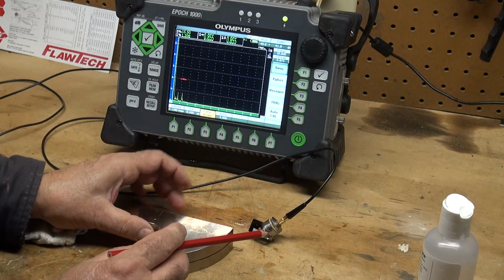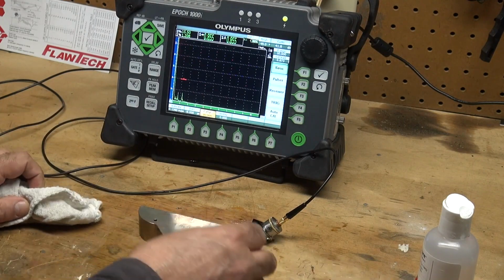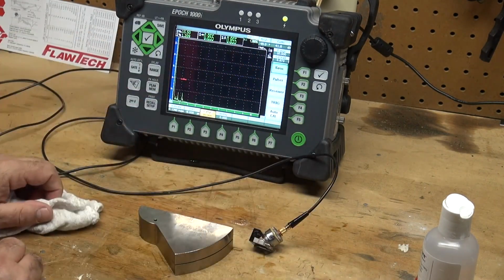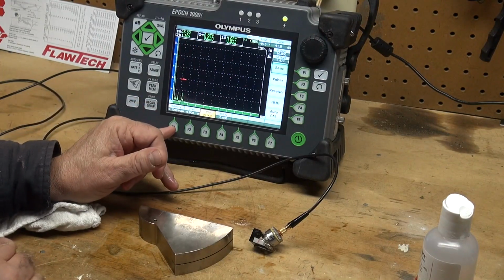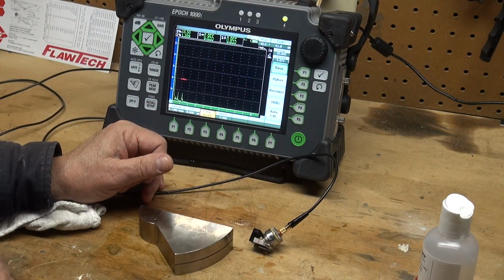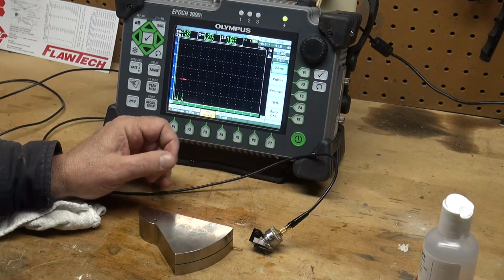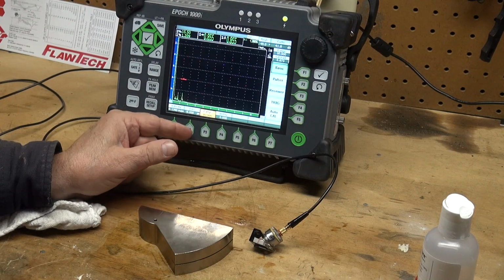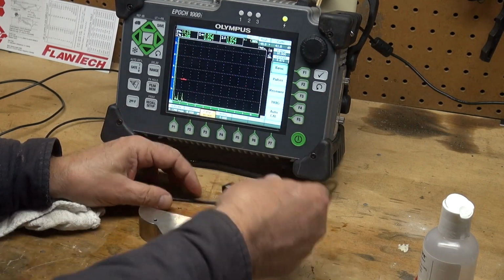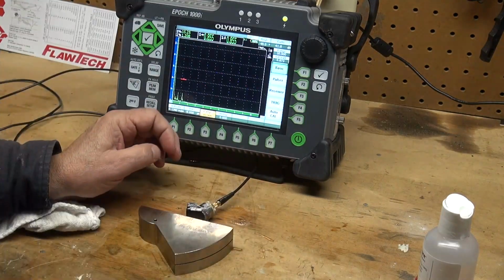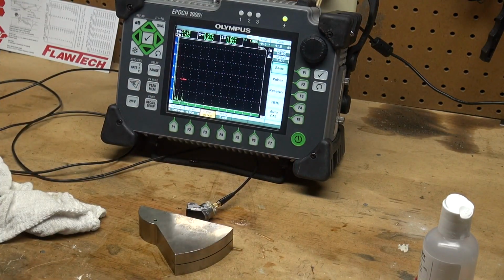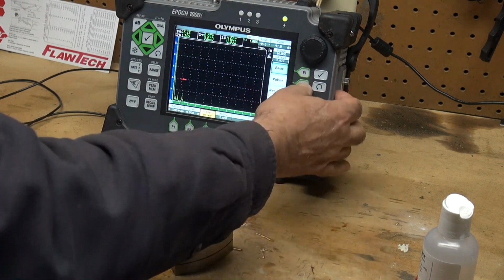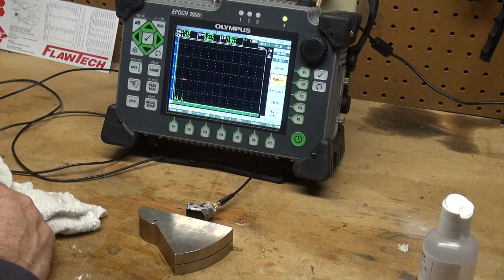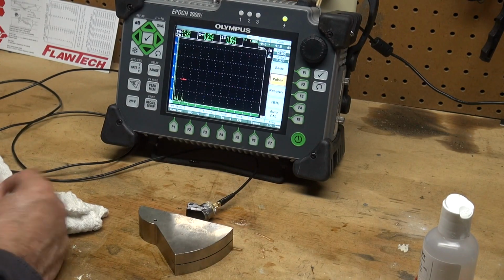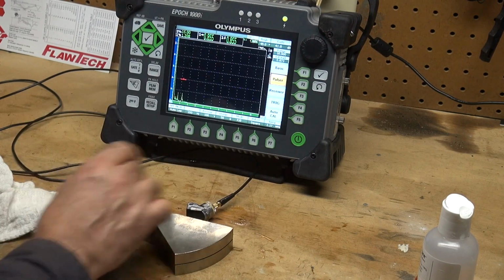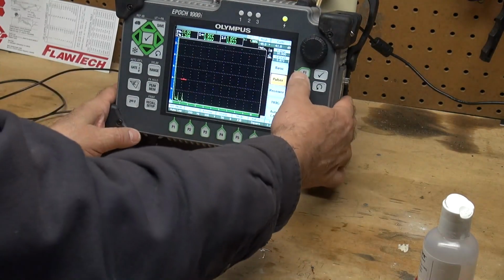Scale here. So let's start by changing the range to 10 inches. Set my screen range at 10 inches. Set my velocity at 0.128 inches per microsecond, your standard shear velocity in mild steel. 0 set to 0. My range is set to 10 inches. And of course, in the trig, I have 45 degree set for my angle. And in my pulser, 2.27 megahertz. I want to make sure that your machine closely matches your transducer frequency.